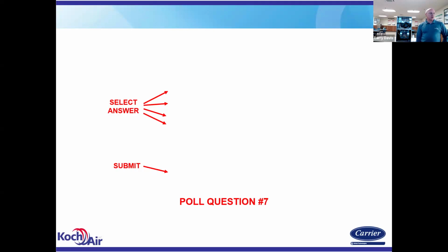All right, during startup, a component test can be performed using the menu on the circuit board. That answer is true. As you scroll through that menu, and it's on the fold-out chart that comes in the furnace as well. If you'd like, I can go over there and get the door for this furnace and show that to you. But you can walk right through there and walk it through the component test. It'll turn the blower on, turn the inducer on, turn the hot surface igniter on. It goes through everything, just like the previous furnace did when you jumpered out the test buttons.